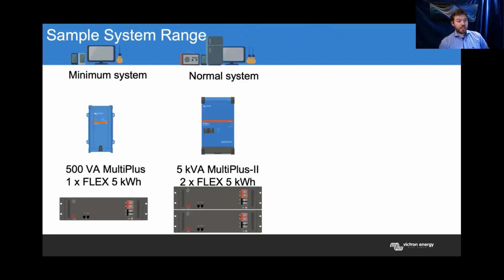So looking at the next system up, a more normal system, let's say, the 5 kVA Multiplus 2, you could probably get away with a single Flex. The Flex 5 kilowatt hour battery can deliver up to 70 continuous amps at 55 volts. That's just shy of the continuous rating of the Multiplus 2. So we'd commonly recommend having 2 of them to make sure there's no chance you're going to potentially overload that battery with a continuous load out of the Multi.